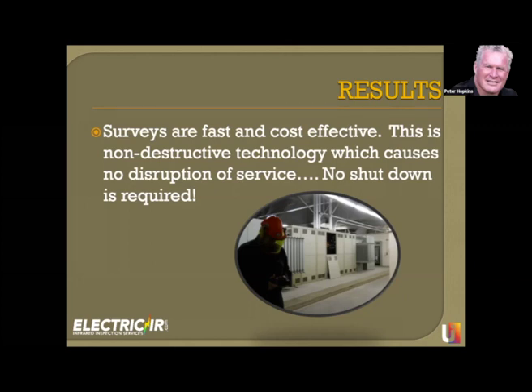These are transformers on each end of these cabinets, and this is your main switchgear room, which is what you'd be looking at here. Usually they'll open up the top or bottom of each cabinet, and once that's clear, it takes me about 2 seconds to look at it. If there's a problem, it takes a couple of minutes because I have to document the location, the cabinet ID, the equipment room, and what we saw — plus any load readings at that time.